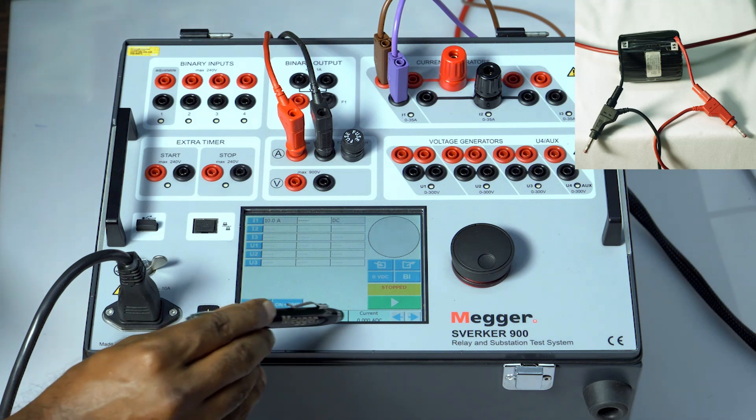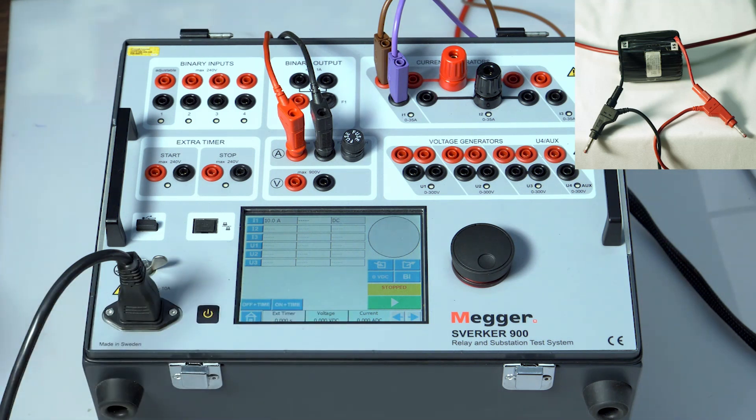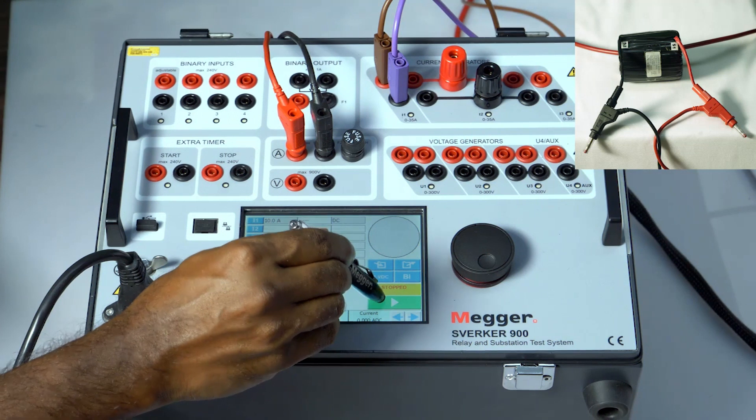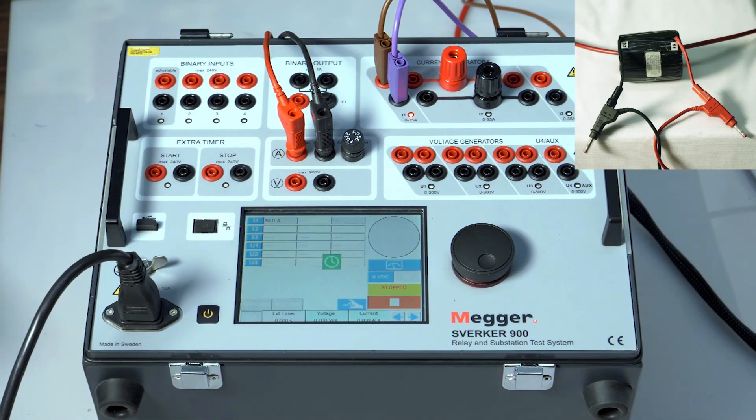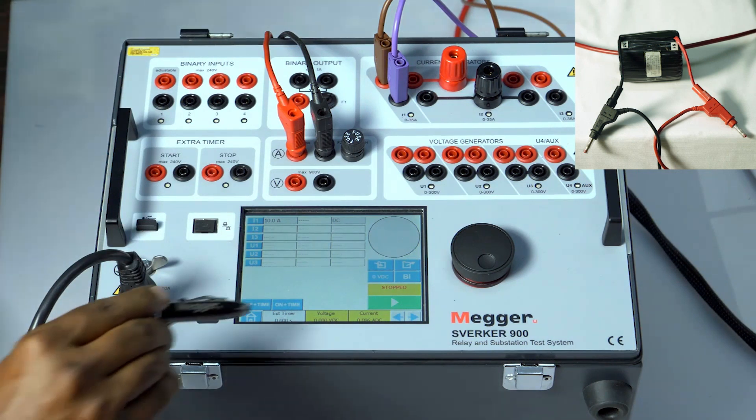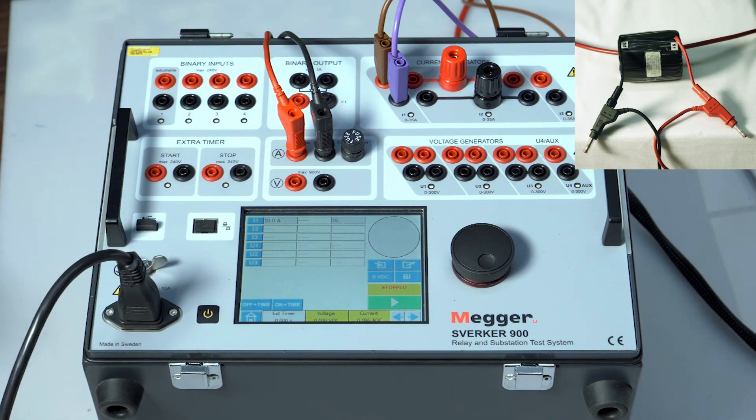Inject the current for approximately one second and switch off. The one second is to ensure that the value gets stable in the ammeter. So let me inject. Stop. You can see the value as 0.086 and it's positive.